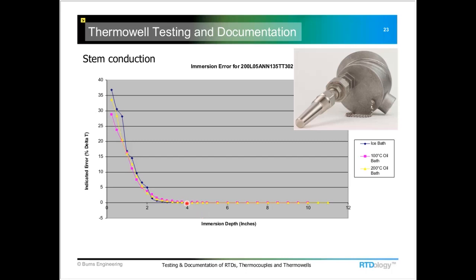And this is all due to the heat transferring from the external components of the temperature probe and the lead wires that lead down to the sensing element, which is at the very tip down here. And so if you have a hot process and cool ambient conditions, it's going to be affected by some of that, have a little bit of a cooling effect on it by the ambient conditions.